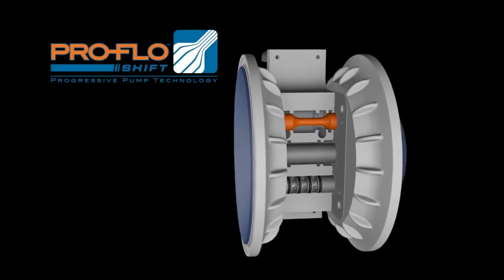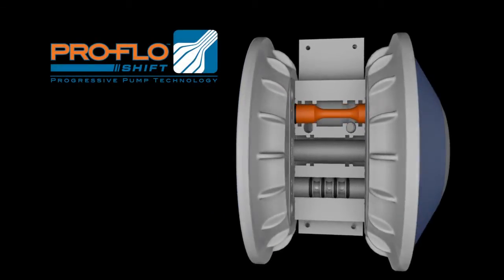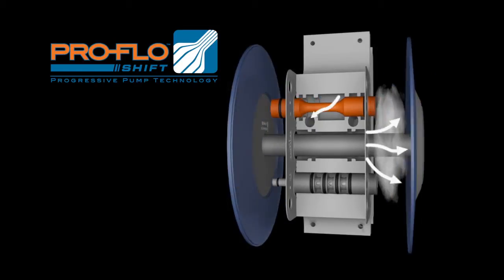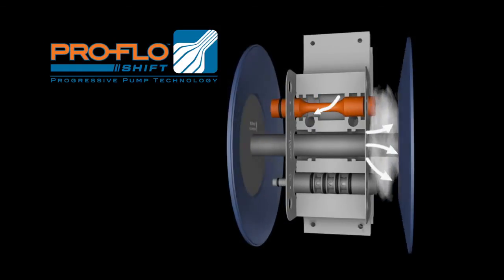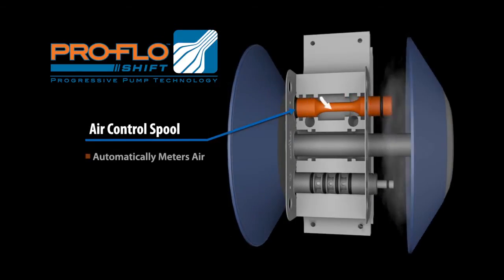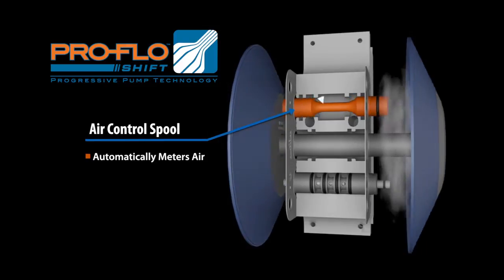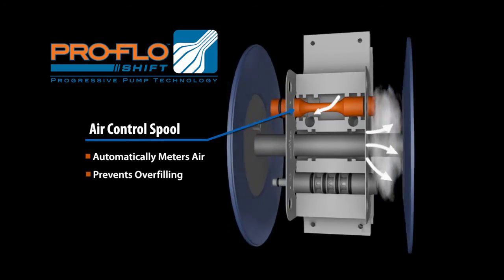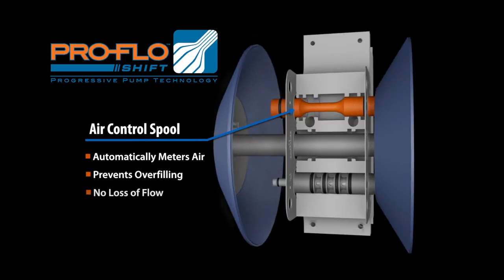Pro-Flo Shift technology is designed to maximize efficiency by minimizing air consumption. This new technology optimizes the pump's performance by using the position-sensitive air control spool, which automatically meters air at the end of the stroke, preventing overcharging or overfilling of the air chamber without any loss of performance or product yield or flow.